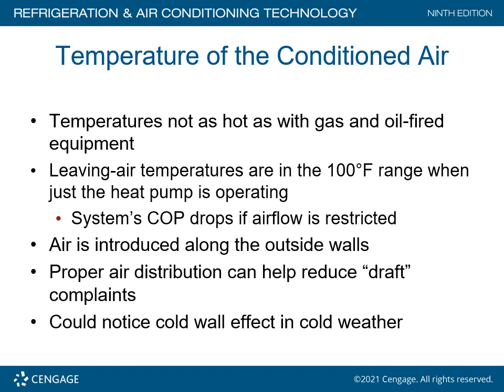Temperature of the conditioned air. The temperature is not as hot as with gas or oil fired equipment. I mentioned this earlier. If you have a heat pump, do not expect a 130 degree discharge temperature coming out of the grill when it is 40 degrees outside. Leaving air temperature is in the 100 degree range. So as an example, let's say you go outside, it's 48 degrees, and on the inside you have the heat pump in heat mode; you're probably going to supply just around 100 degrees. When I do temperature split checks in heating mode, typically I would expect to see on the supply side about 100 degrees, not 120, not 130, like you would on a gas-fired system, or oil fired for that matter.